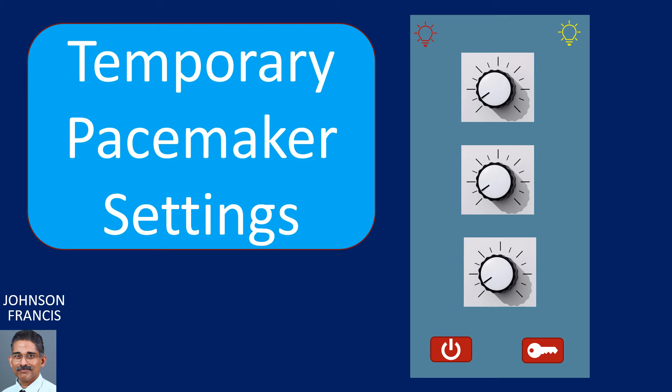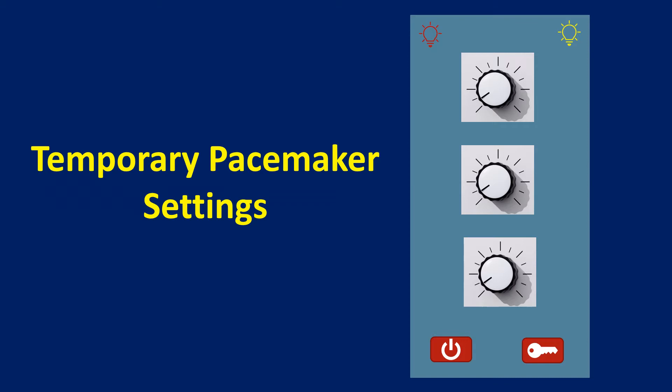This is an accompanying video for the previous video on temporary pacing available on this channel. This video will describe the basic temporary pacemaker settings. The controls and buttons shown here are symbolic and vary between different models of pacemakers. Some pacemakers have a display of the modes and parameters in addition. This description is on a commonly used single chamber temporary pacemaker. Dual chamber temporary pacemakers will have additional controls and displays.